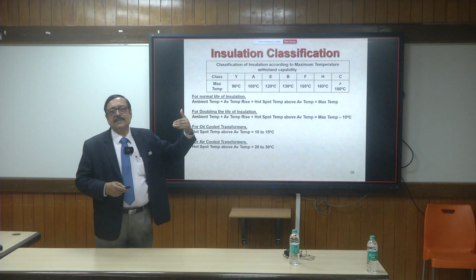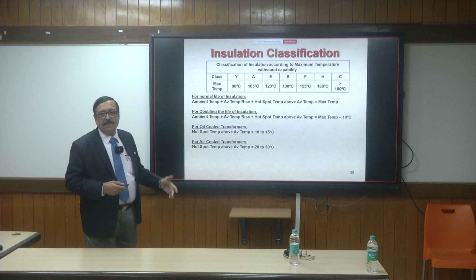the core characteristics. If you take the temperature of the core beyond its Curie point, it will lose its magnetic property as it had. So you have to be very cautious about the Curie temperature and the temperature, and therefore the class of insulation you're using and the curing temperature. Otherwise your perfectly designed product will land up with a catastrophe.